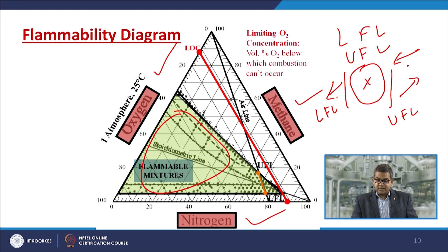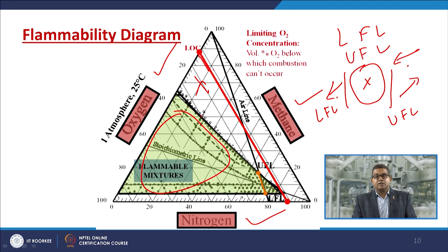The limiting oxygen concentration says it is the volume percent of oxygen below which combustion can't occur. That means there is no adequate supply of oxygen to meet the stoichiometric demand. If you recall the chemistry formula, CH4 plus 2 O2, if you are increasing the amount of nitrogen, it will not cross this limiting oxygen concentration mark. Now this is the safer zone. So whenever you have such a scenario, you must calculate up to how much quantity of inert material is required so that it does not cross this LOC barrier or the LFL line.